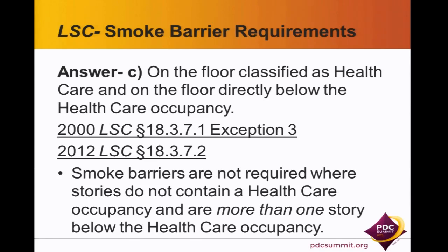Is that the case even if you're egressing directly outside? Yes. Yes, it's not an egress-dependent issue. The concern the committee has is if the fire's on the floor below, and your emergency plan has us moving patients to the other side. If there's no barrier on that floor below, we can then get vertical smoke spread on the other side of the smoke barrier. Now, there's an interesting challenge here that we've started to encounter more outside the U.S. than inside the U.S., where there's a number of healthcare facilities with parking directly below the ground floor, which is a healthcare occupancy. Good luck putting a smoke barrier in a parking garage.